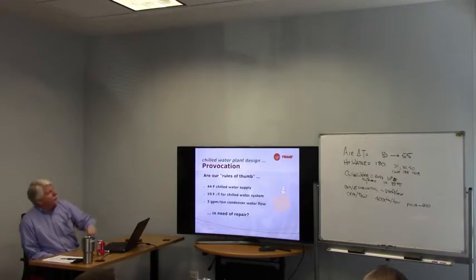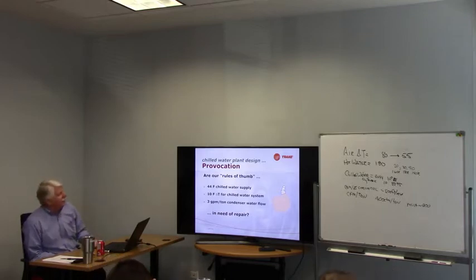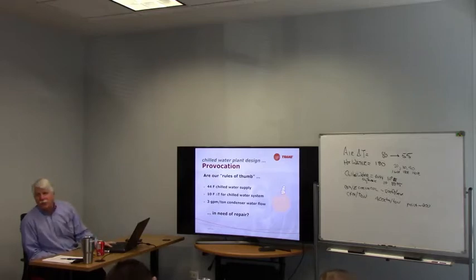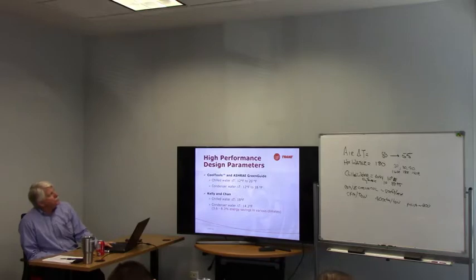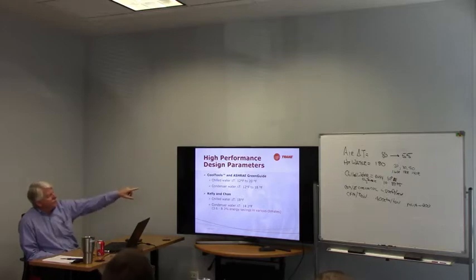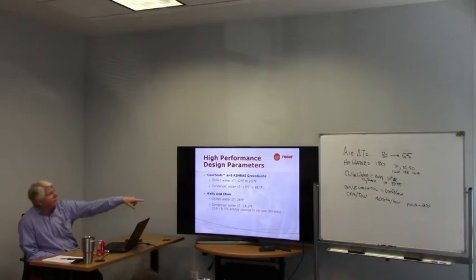Now these are the rules of thumb I had over here. 44-degree chilled water, 10-degree delta T, what's called 3 GPM for condenser flow, which is a 10-degree condenser delta T. And the question is, should we be using those today? In some studies that were done by ASHRAE and another study from a company called Kelly and Chan, they're saying chilled water should be anywhere from 12 to 20 degrees. They're saying 18-degree delta T. And condenser water should be from 12 to 18, and they're saying 14.